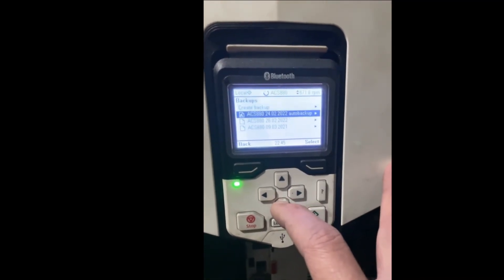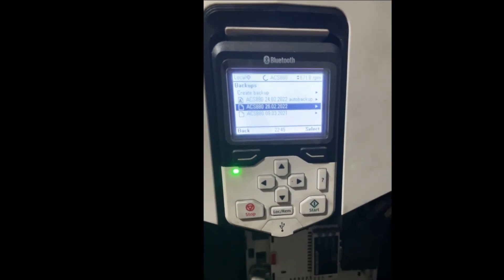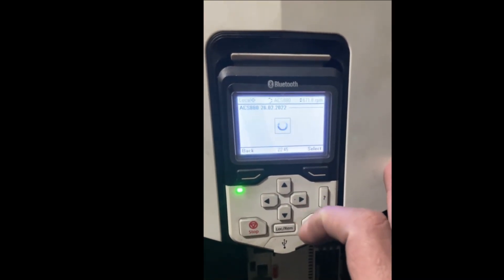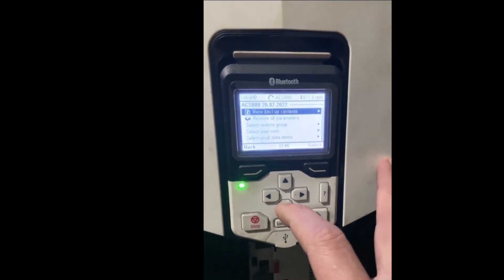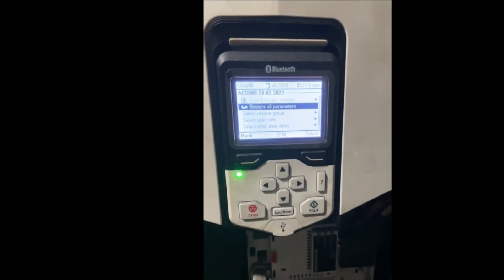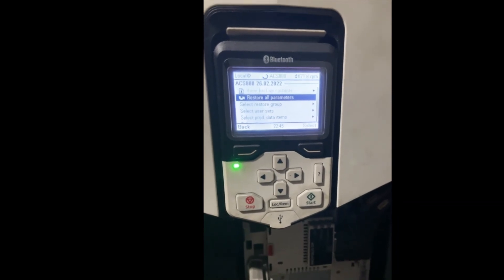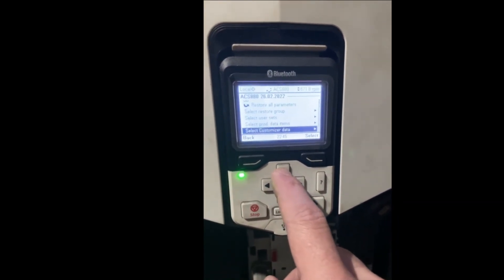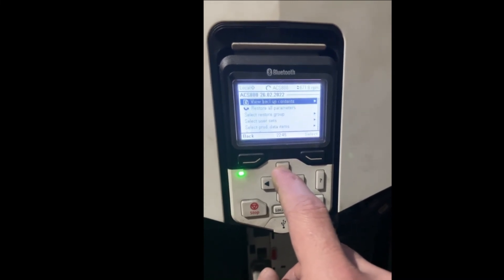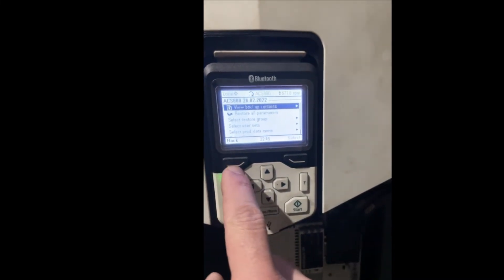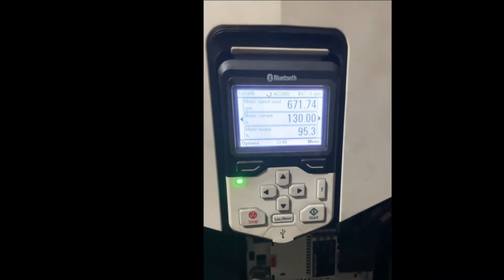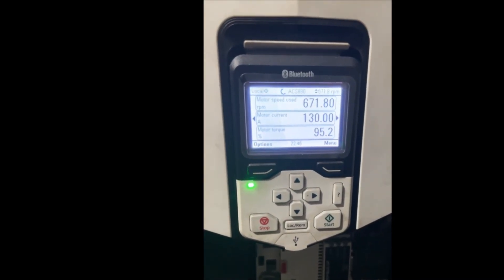If we want to restore that backup, we come back to this screen, go to whichever copy we want to restore — the new copy or the old copy — highlight it, press Select, and it will give you an option. You can restore all the parameters, or you can restore a specific parameter or specific group of parameters if you don't want to restore all of them. When you're done, just keep pressing Back to exit and go back to the main screen. And that's how you copy the parameters.